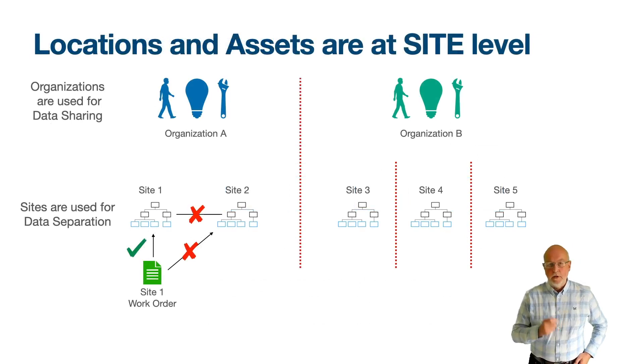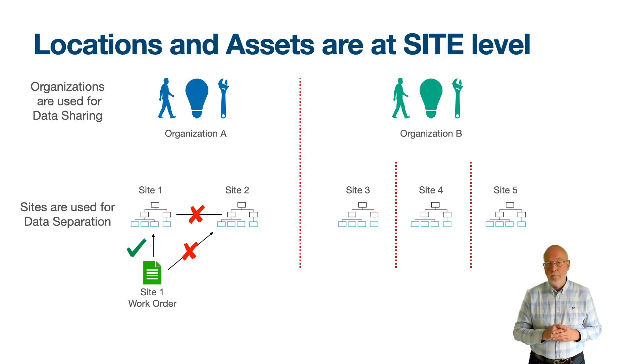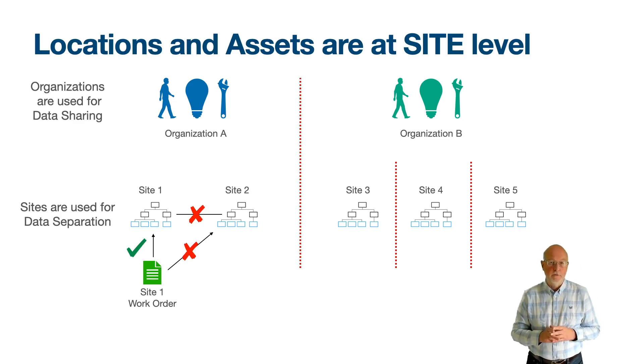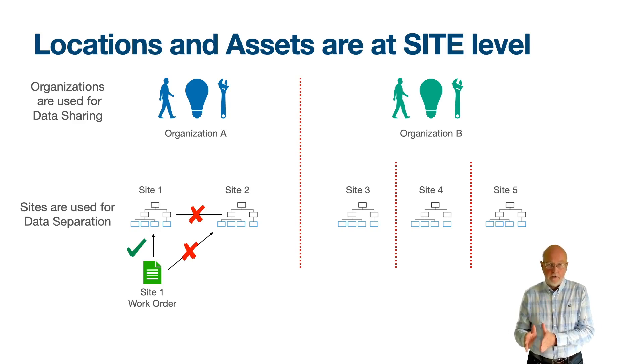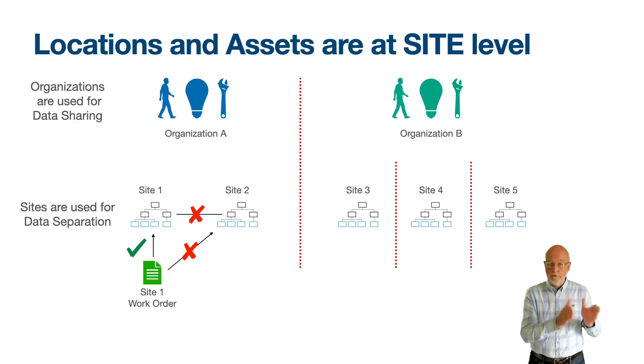Locations, like assets, are site-level objects. In Maximo's multiple organisations and sites data structure, a site is for data separation and an organisation is for data sharing. Locations and assets cannot be related to locations in different sites, cannot contain assets from other sites, or be referenced on work orders for other sites. A work order for the Bedford site can only reference work to be performed on locations and assets on the Bedford site — there is data separation between the work performed on one site from the work performed on other sites.